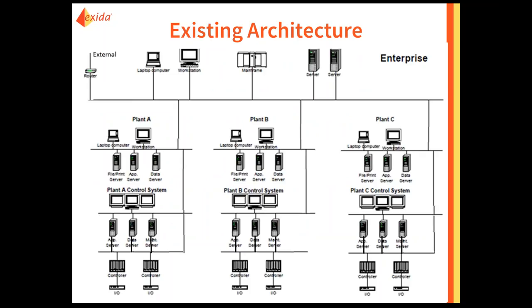As an extreme example we have seen in the field: enterprise architecture goes out to the Internet, three plants connect to that enterprise architecture down to the control system, and from there straight down to layer one and layer zero devices — your PLCs and I/O. Also at the layer two level there are dual-homed servers connecting two separate networks, which is the least secure segmentation method, allowing threats to propagate across both networks.